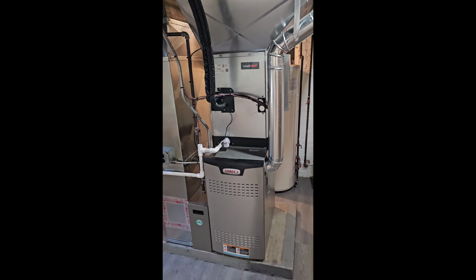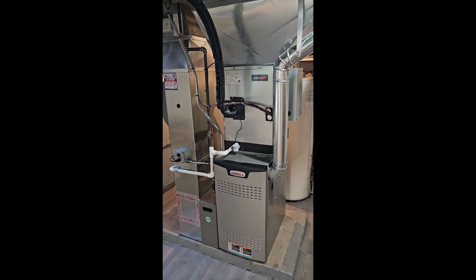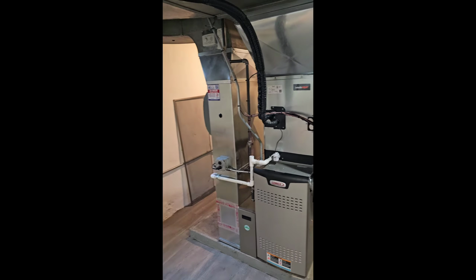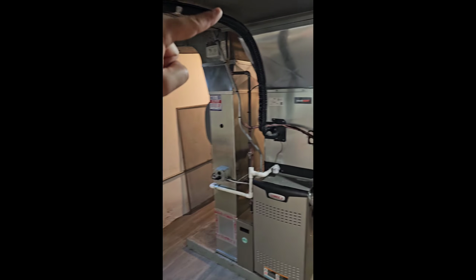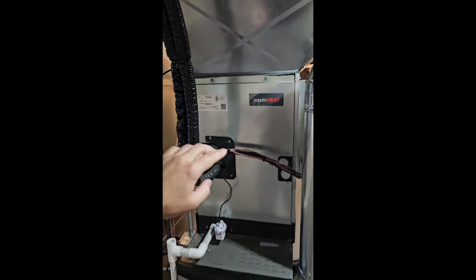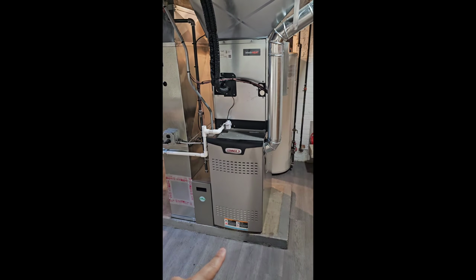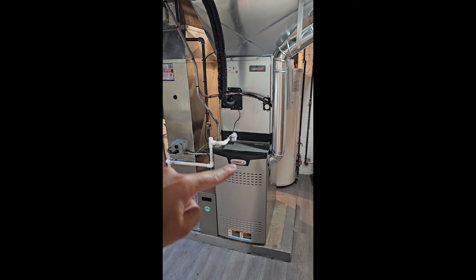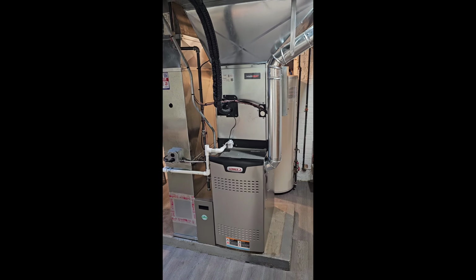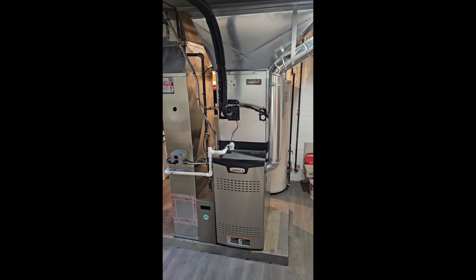The way this works is whenever the temperature outside is 32 degrees or higher in the winter, our outdoor unit is going to be bringing hot refrigerant and warming up our IntelliHeat coil. And all the furnace has to do is run the blower to circulate air across our hot coil and bring heat into the home through the existing ductwork.